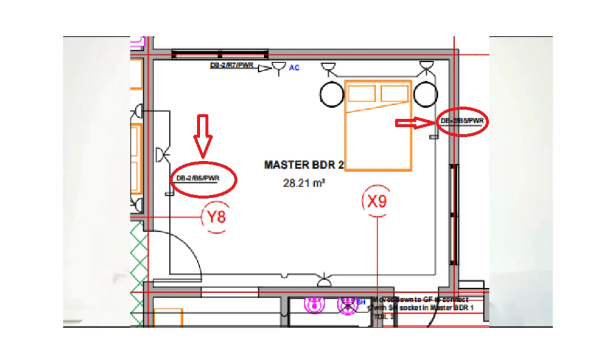circuit. It's very important. So if we are talking of lighting systems, small power systems, equipment parts as well, we'll be having different circuits, such as maybe we have a DB, which have different ways, and then we have maybe a three-phase supply, which is RYB phase in the case of Qatar or in the case of the British standard. So looking at the different phases on the drawing as well, it will be represented as probably R1 circuit, R2, R3, R4, Y1, Y2, Y3, Y4, and then we have them as they keep going based on the number of ways of that distribution board.